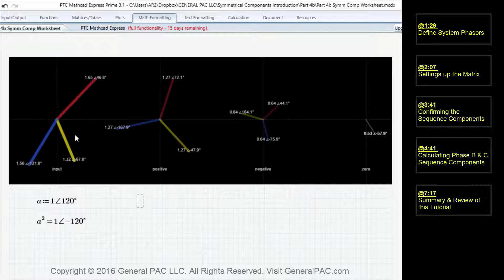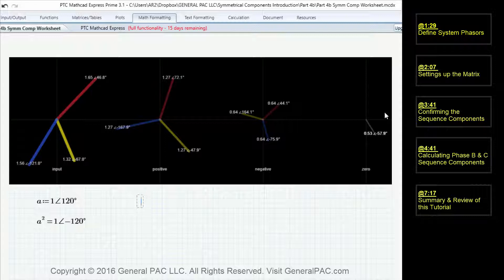Our system phasor has an ABC phase rotation. The positive sequence component also has the same phase rotation as the system phasor, so it also has an ABC phase rotation. The negative sequence component is always the opposite, so we can expect this to be an ACB phase rotation. The zero sequence component — although all three phasors rotate counterclockwise — doesn't necessarily have a phase sequence.